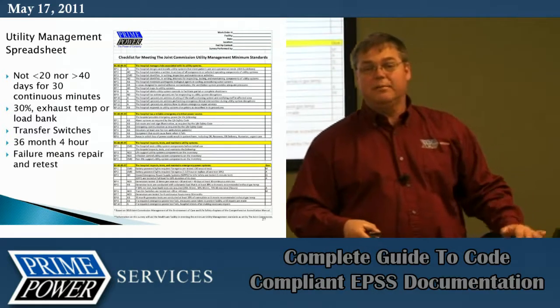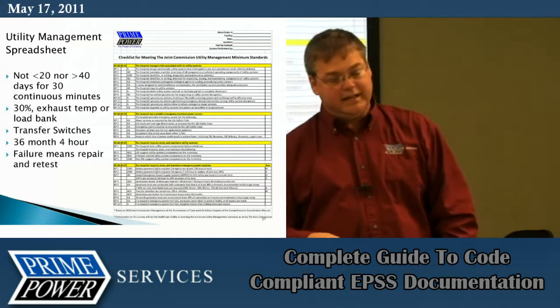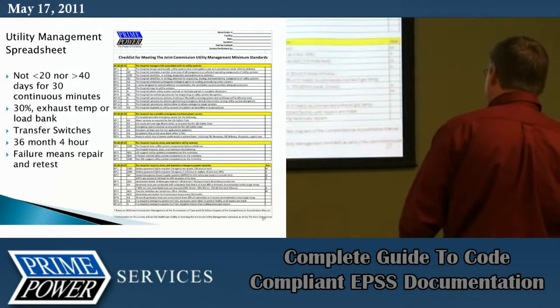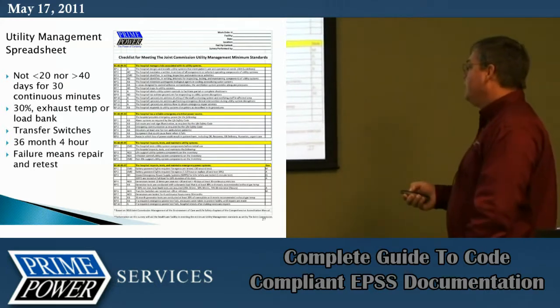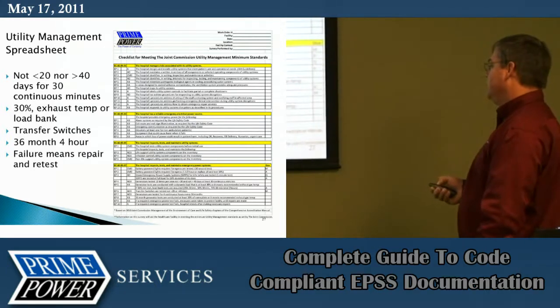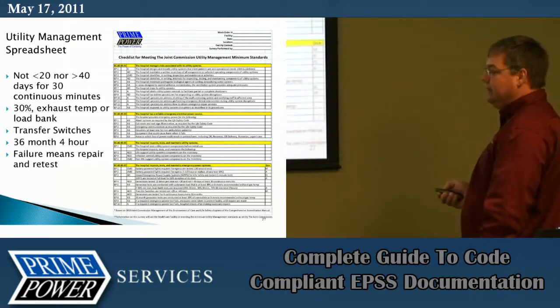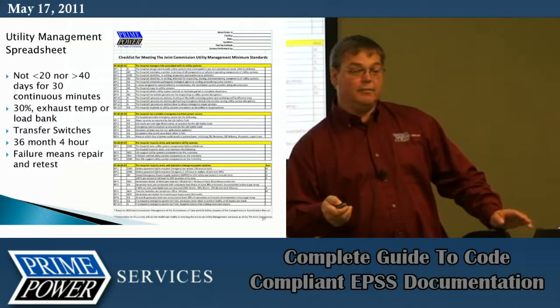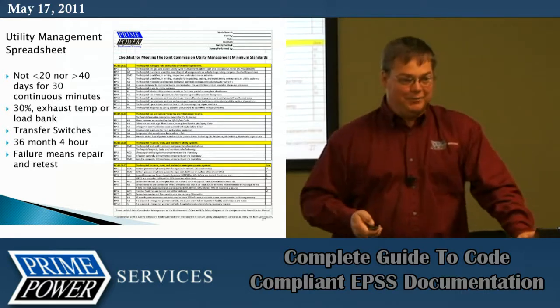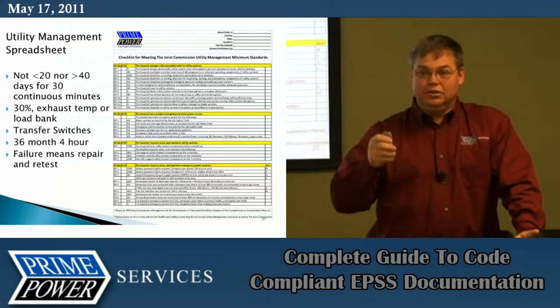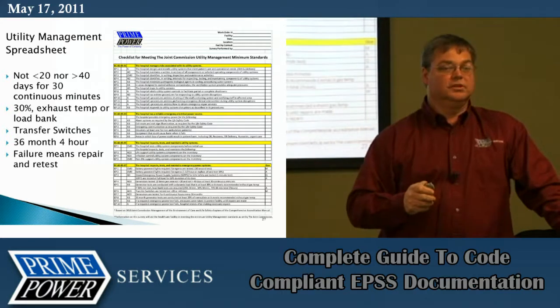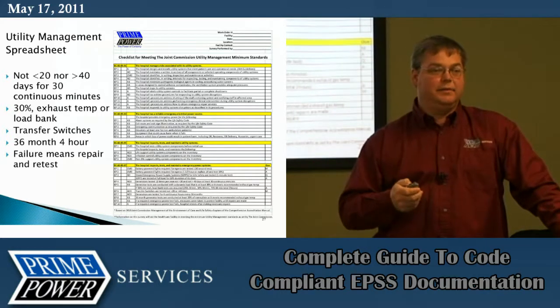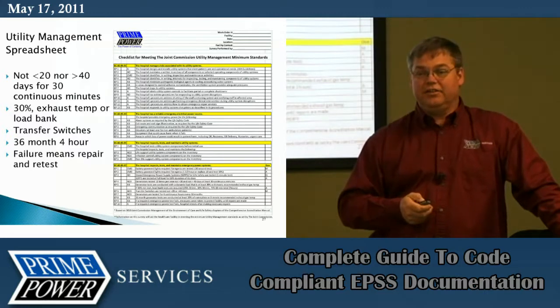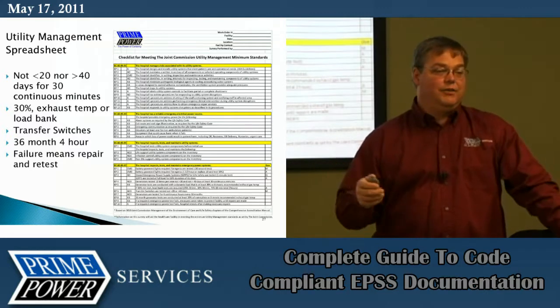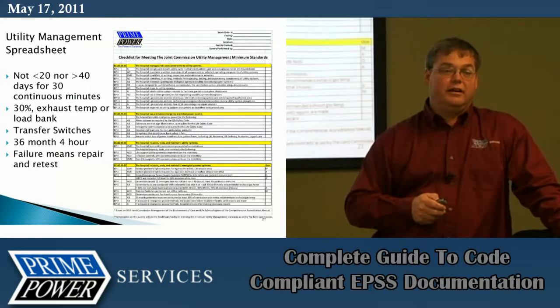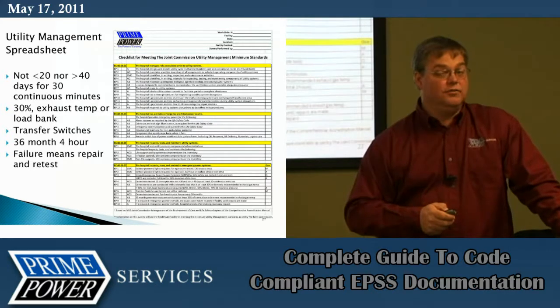All right. Failure means repair and retest. Again, Joint Commission standard. This was added in 2010. If a required emergency power test fails, measures were taken to protect the facility until the repairs are made. Everybody ever heard the term interim life safety measures? This comes into play. If you have your generator system fail, you've got to do something immediately to protect the people in there. You know, if you're a facility that has another one that has a backup, great. If you're a facility that only has one and your generator is not reliable to crank, you've got a problem.